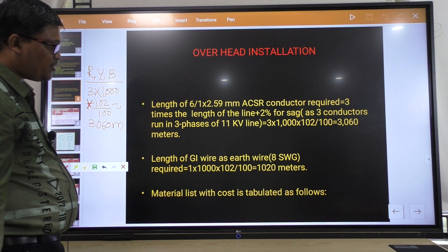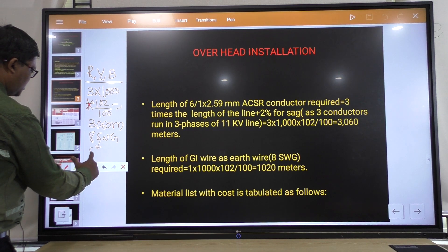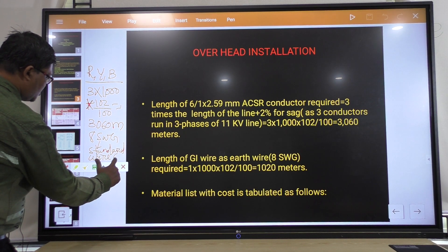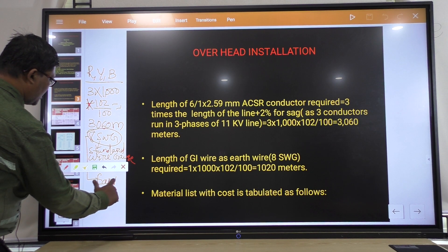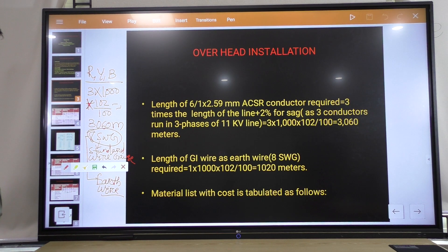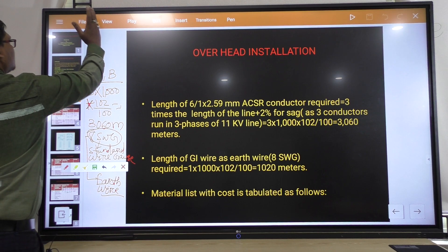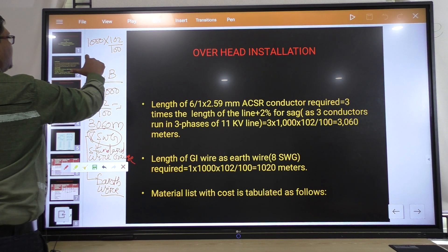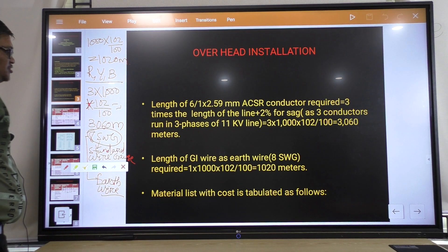Next, the length of GI earth wire. The standard earth wire specification is 8 SWG — Standard Wire Gauge. 8 SWG is the standard for earth wire. The length of earth wire will be total length 1000 into 102 by 100, that is adding 2 percent sag. It comes to 1020 meters of earth wire required.